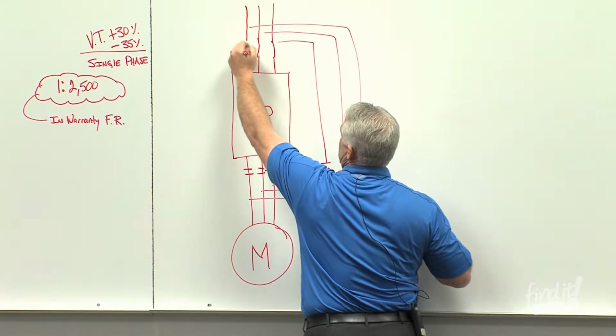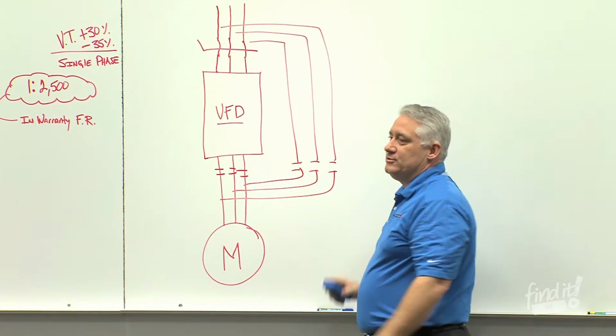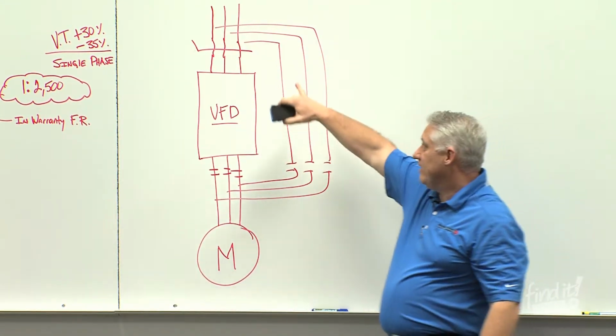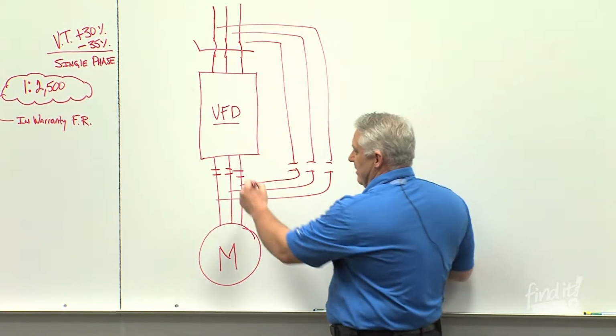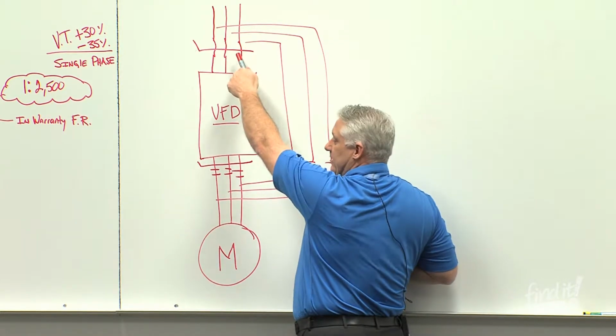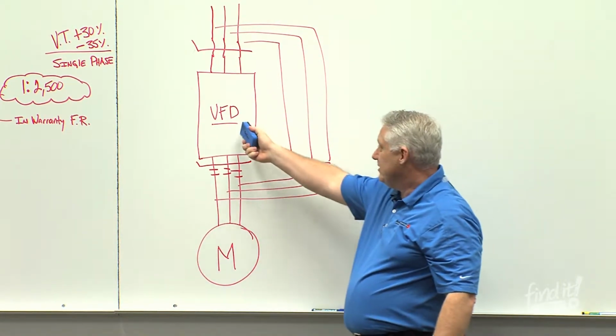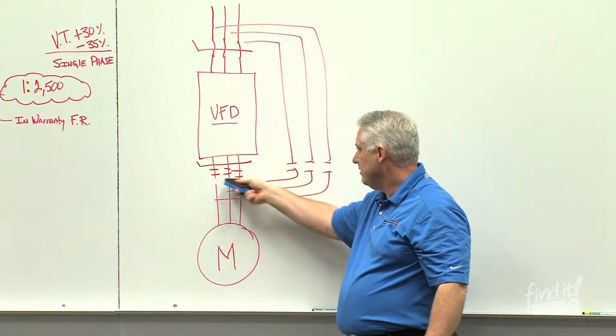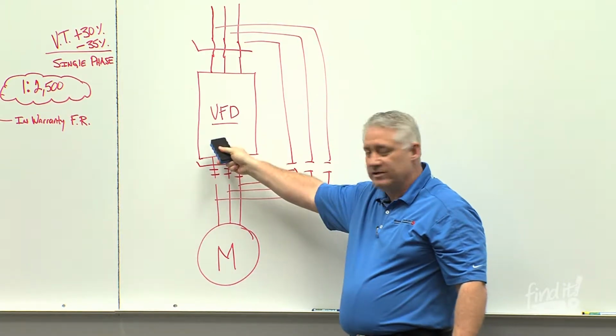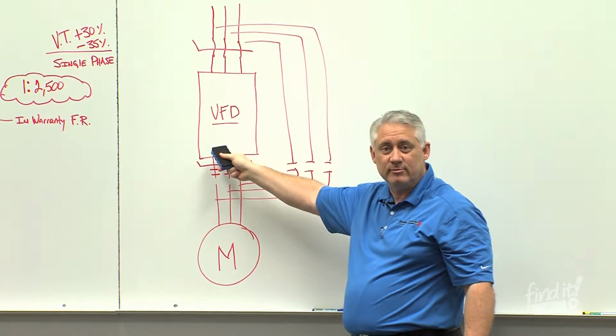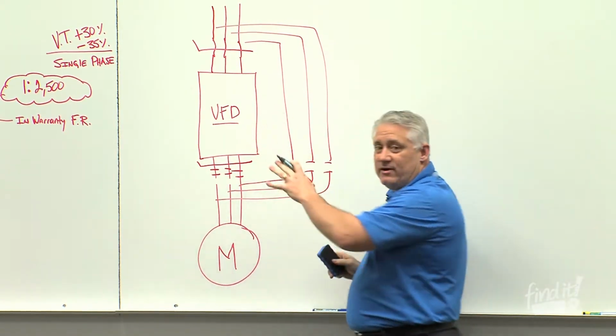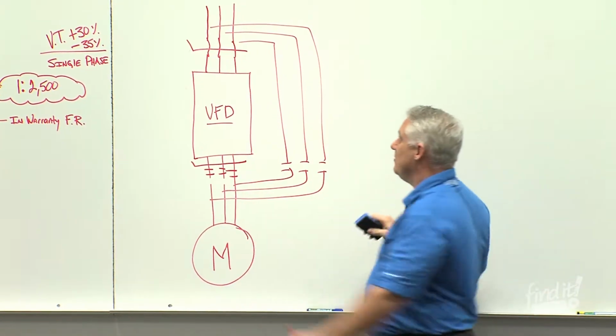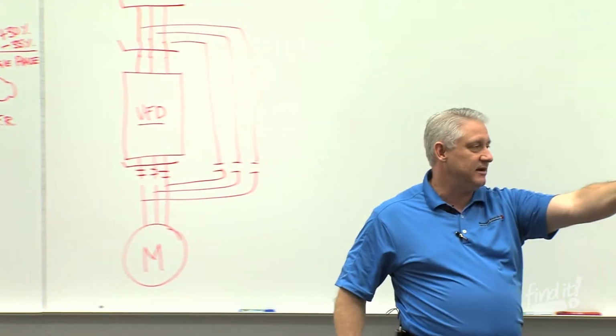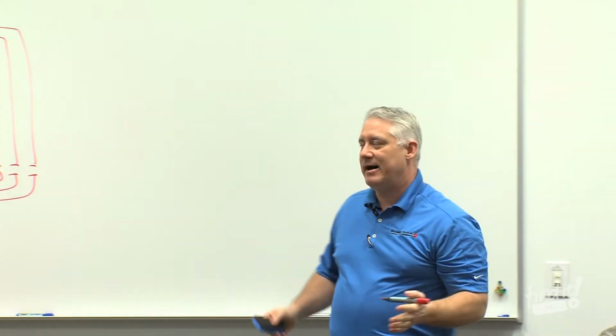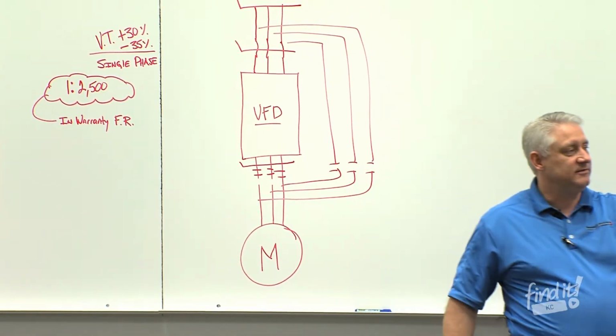Now, people still wanted to have a sense of security, so drive manufacturers added an optional service isolation switch to the front end of VFDs. But what they really neglected to do was add another one down here below. Because if you can kill yourself here, you can kill yourself here too, right? If you're working on this device and we have it in bypass, there's 480 volts right here. If you accidentally bump the plunger on that contactor, you can send AC voltage into the DC side of the drive and you can kill yourself. It'll blow up in your face. So really, it's a false sense of security adding that service switch inside of the box. You still want to have the main service disconnect switch, which is on the outside of the box. Richard, will you point to that? That kills power to the entire box, with the exception of where power hits the line side of that disconnect. So that's really how it's evolved.